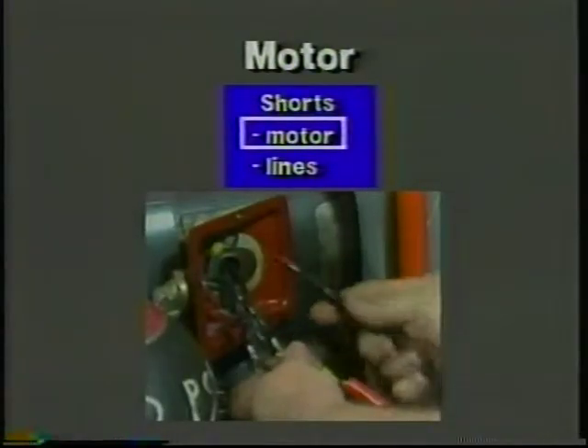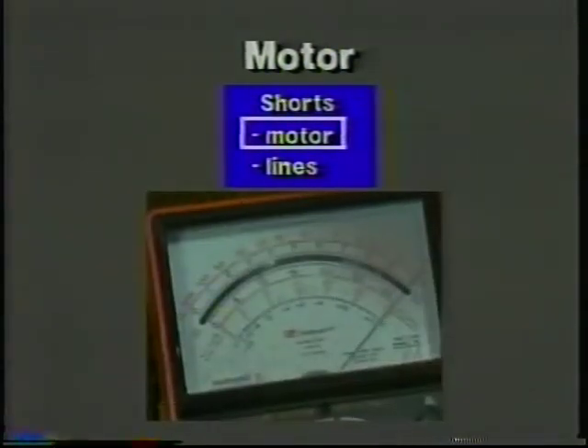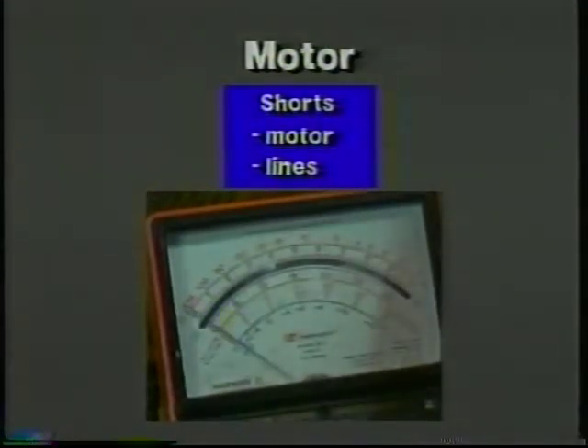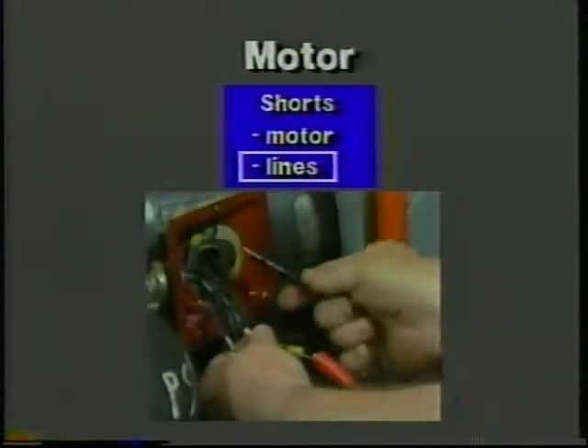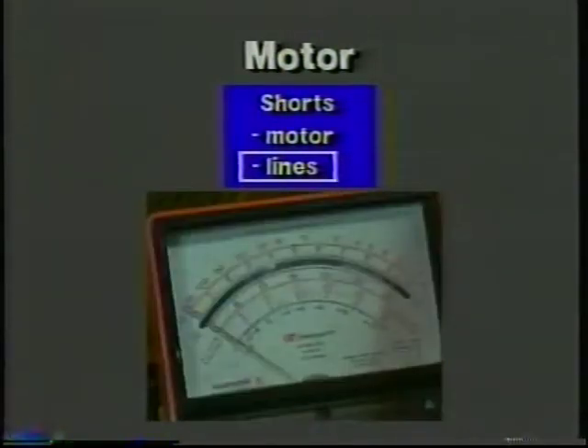Now a short to ground will show up in a resistance reading on the motor, but a short between the windings may not, since a motor's resistance is normally very low anyway. If you cannot identify the short in the motor, try to rule out the lines. Check their resistance to ground and to each other. Infinite resistance readings eliminate them.